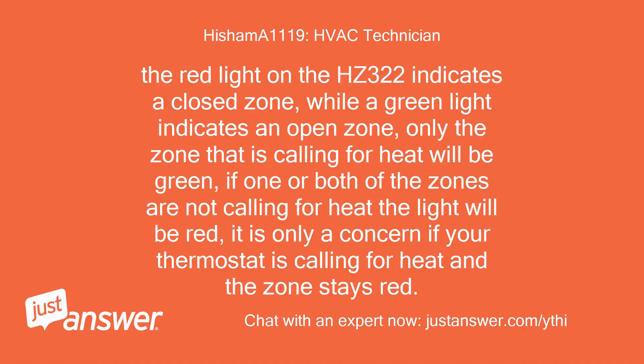The red light on the HZ322 indicates a closed zone, while a green light indicates an open zone. Only the zone that is calling for heat will be green. If one or both of the zones are not calling for heat, the light will be red. It is only a concern if your thermostat is calling for heat and the zone stays red.